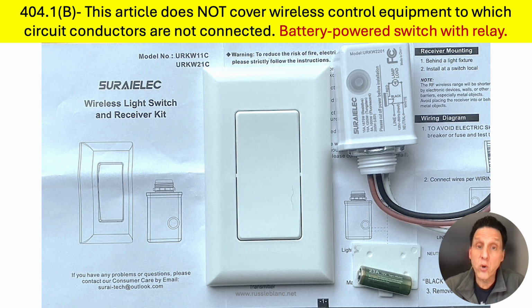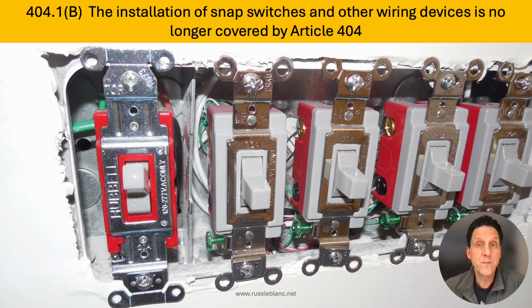These are permitted to control lights. There are some provisions in 210. I'm pretty sure it's 210.70 that does make mention of battery-powered switches. So you can use these types of devices. They're just not covered by 404 any longer. Or actually, they never were anyway, because there are no circuit wires connected to them. And they still won't be covered.